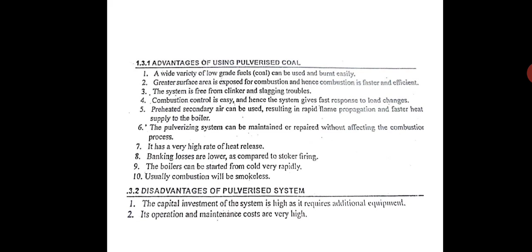Now the disadvantages. Because the coal is pulverized, the capital investment of the system is high, it requires additional equipment for pulverization, and its operation and maintenance costs are also very high. It also produces fly ash and dust because it is very fine. Nowadays, due to very stringent environment pollution control norms, you require fly ash removal equipment like ESP, that is electrostatic precipitators. The Government of India, through the Pollution Control Board, has made it mandatory to have these ESPs.